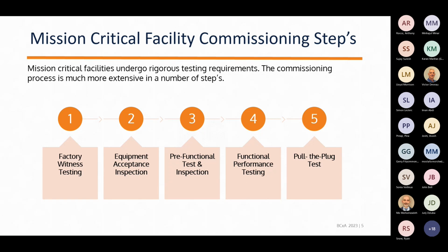Factory witness testing is very important to a critical environment for a number of reasons. It's usually outlined in the testing protocols in the bid submission by the engineer. We usually have an engineer, a commissioning agent, or a representative of the owner present when doing factory witness testing on a generator, ATS, transformer, or any big primary piece of equipment like chillers. We want to make sure by the time they get into that critical environment, they're working and in good order.